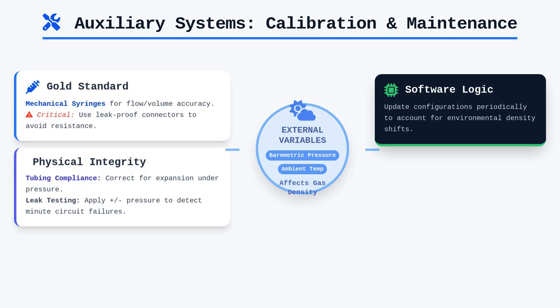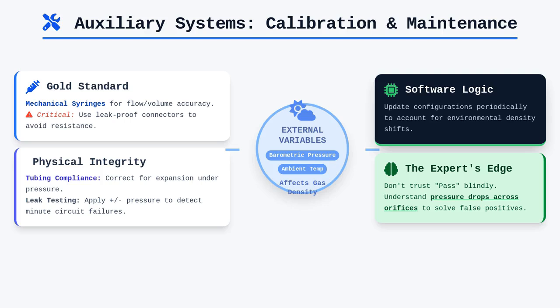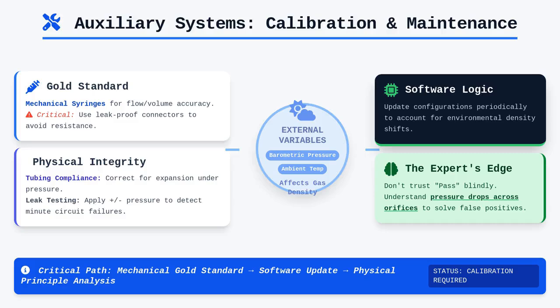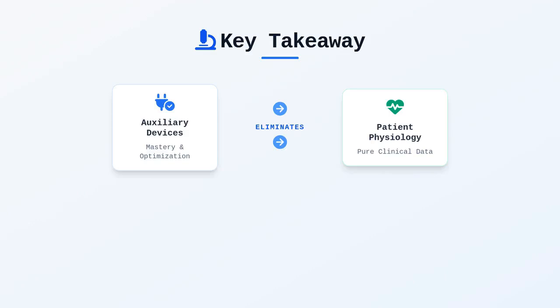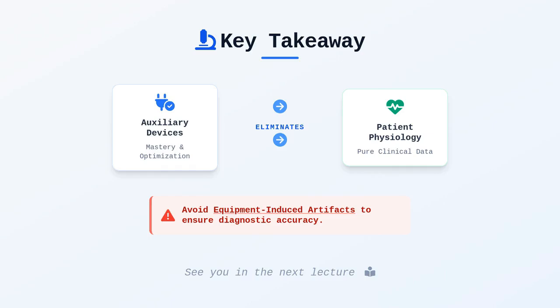Furthermore, equipment software calibrations must be updated periodically to account for environmental factors like barometric pressure and ambient temperature, as these variables affect gas density and, consequently, the accuracy of our flow measurements. Relying on automated software checks is a good starting point, but a true professional understands the underlying physical principles, such as the relationship between gas density and pressure drops across restricted orifices, to troubleshoot discrepancies effectively when the software reports an error or, worse, provides a false positive pass. In short, mastering these auxiliary devices ensures that your laboratory data reflects the patient's physiology rather than equipment-induced artifacts.